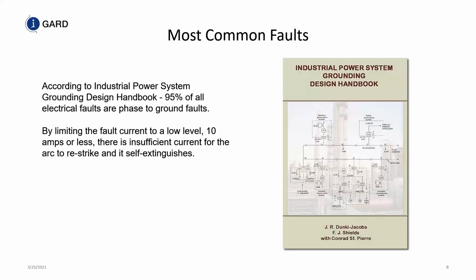As a matter of fact, it is very difficult for a three-phase bolted fault current to occur all by itself, unless, and I hear this more often than not, somebody leaves the grounds on after maintenance and you energize the gear, or you open up a panel and steel falls across three phases. A forklift drives through a bus duct. It's very rare that it's going to occur by itself.